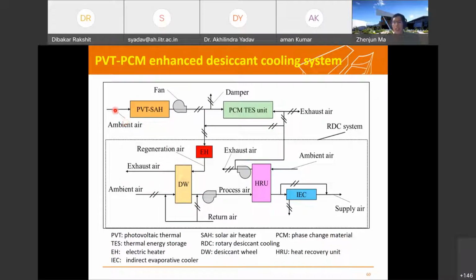So we have thermal energy storage sitting here for the heat from the solar air PVT, and the solar air heater can be directly used to regenerate the desiccant wheel, or can be used to charge the PCM storage and then used later for regeneration of the desiccant wheel. This is the electrical heater - if the heat or temperature is not enough, we can use this device to provide sufficient heat.